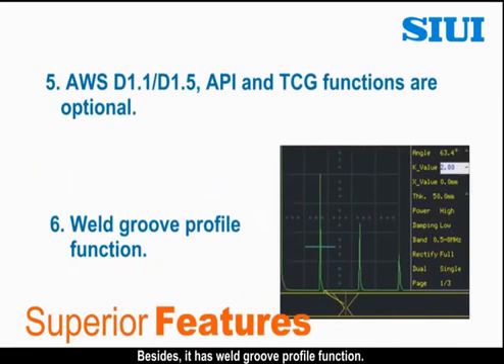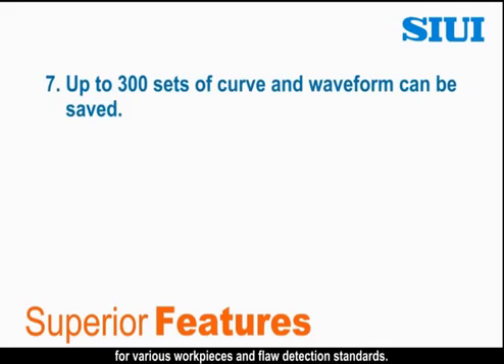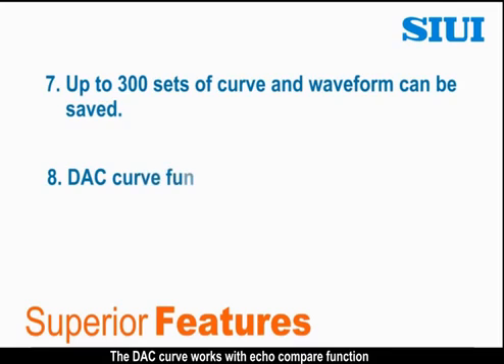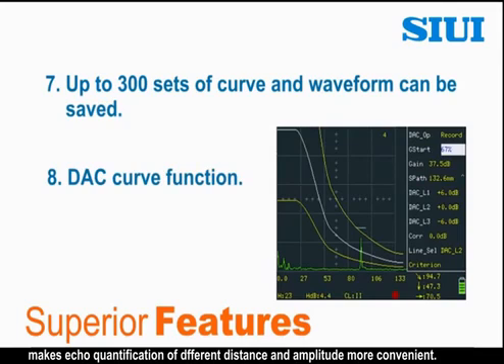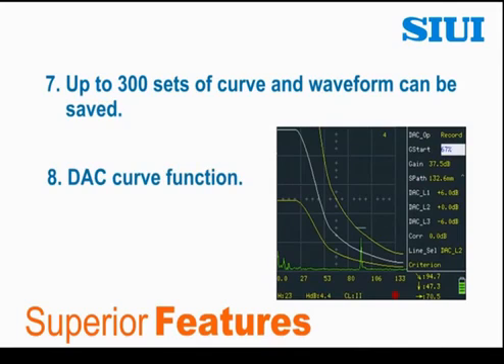Besides, it has a weld groove profile function. Up to 300 sets of curve and waveform can be saved for various work pieces and flaw detection standards. The DAC curve works with echo compare function, making echo quantification of different distance and amplitude more convenient.